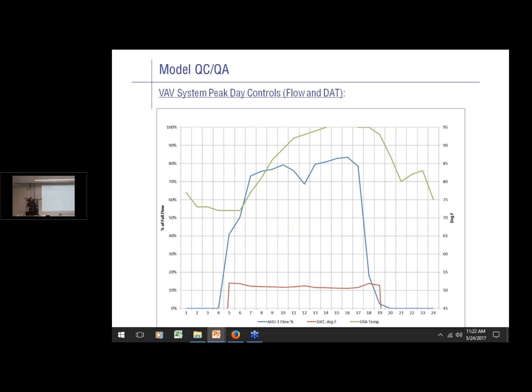We are seeing a load reduction at noon. So by implication, I would say somehow the modeler has plugged in some people leaving, some lights turning off, some other things happening in the zones. Maybe that's appropriate. Maybe it's not appropriate. We peak in the afternoon and then we drop. So the blue line doesn't bother me too much.